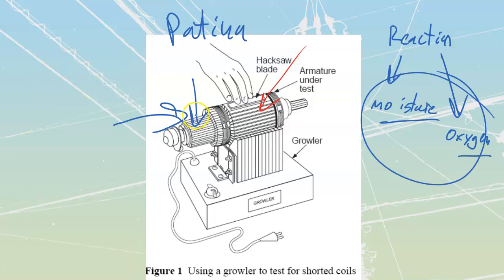A DC motor or anything that has got a commutator is not placed into vacuum because if I'm inside of a vacuum, we are going to lose moisture and oxygen. Where this actually came from is actually World War II high altitude bombers. Once they started to push their bombers much higher, they found that anything that was electric motors was only lasting a few bombing runs.